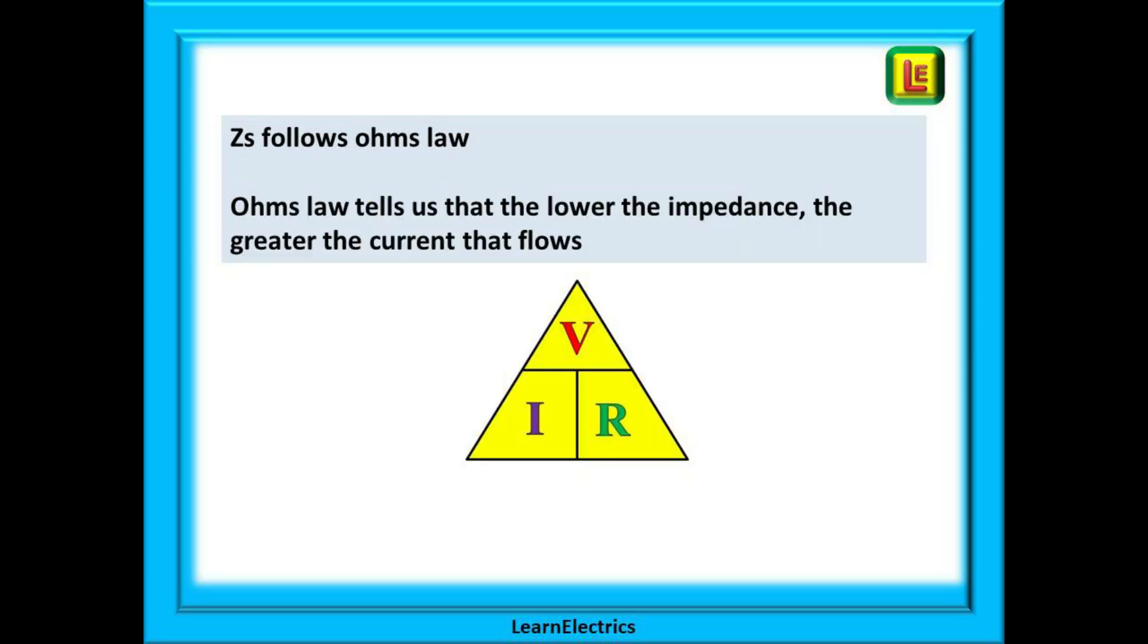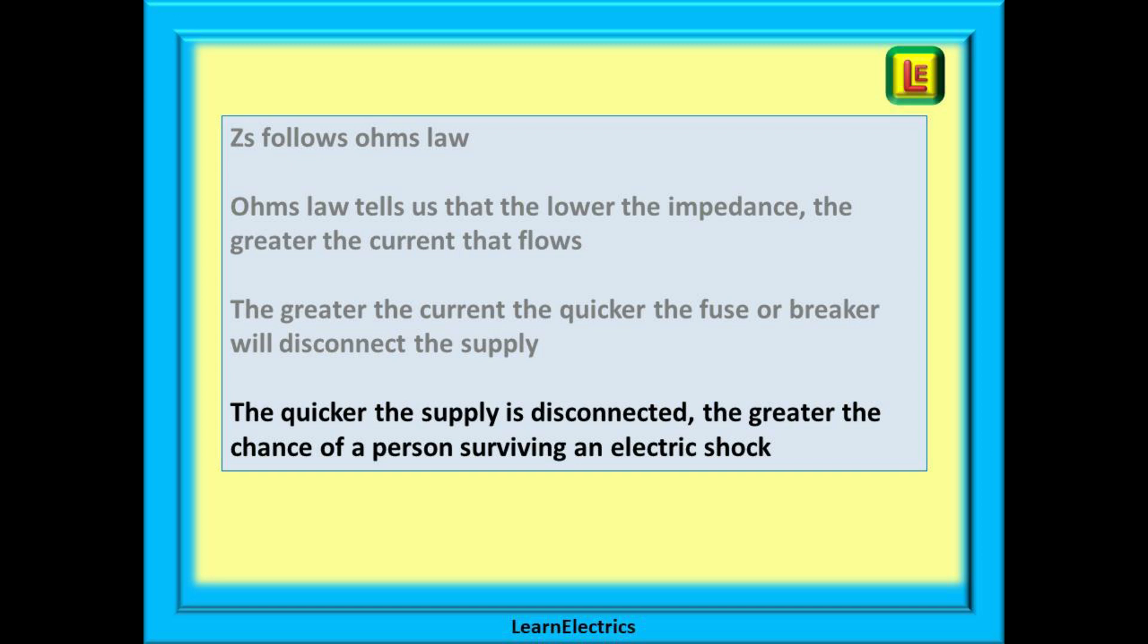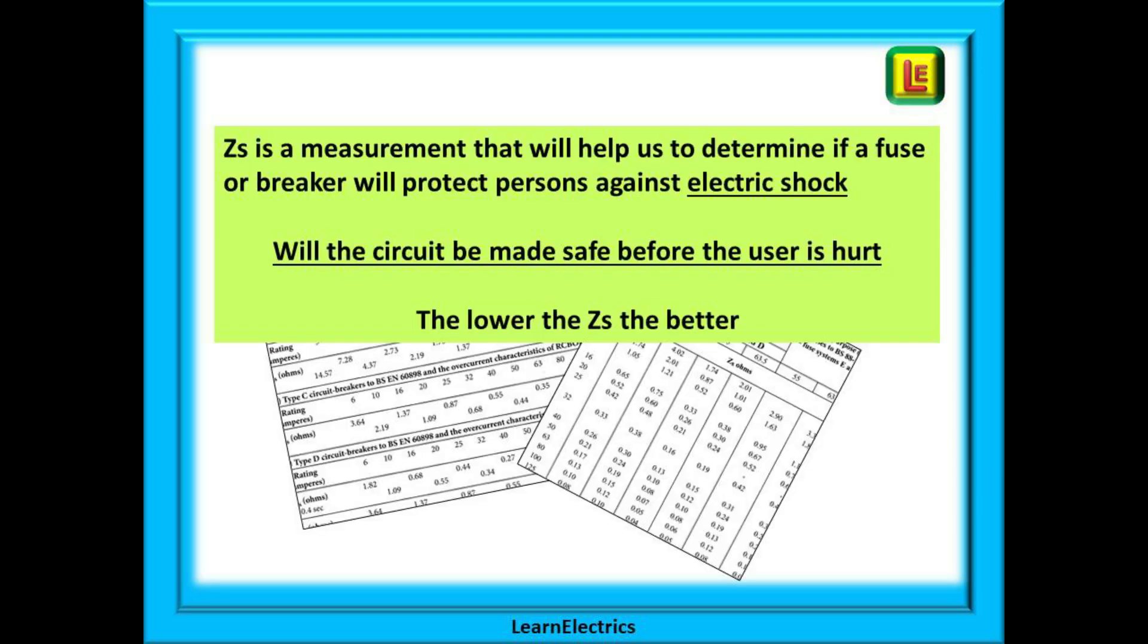Ohm's law tells us that the lower the impedance the greater the current that flows. Impedance down, current up. The greater the current that flows the quicker the fuse or breaker will disconnect the supply, so we want big currents to flow during a fault. And the quicker the supply is disconnected, the greater the chance of a person surviving an electric shock. ZS is a measurement that will help us determine if a fuse or breaker will protect persons against the dangers of an electric shock during a fault. Will the circuit be made safe before the user is hurt? The lower the ZS the better because this means bigger currents and quicker disconnection times.